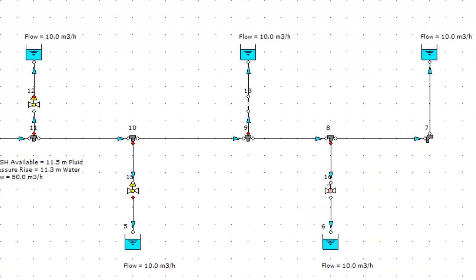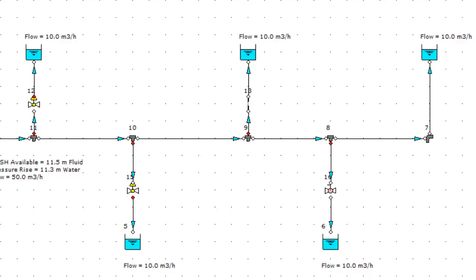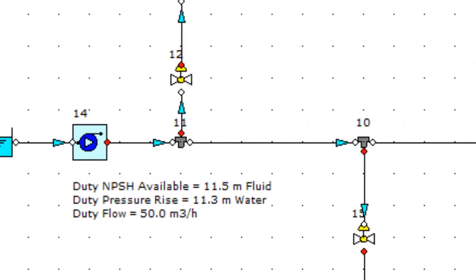You can now see that our flow distribution remains unchanged. We are still getting our required flow rate to each offtake. We can look at the auto booster results, and see that we have a duty point with which we can now approach pump OEMs to select a suitable pump.